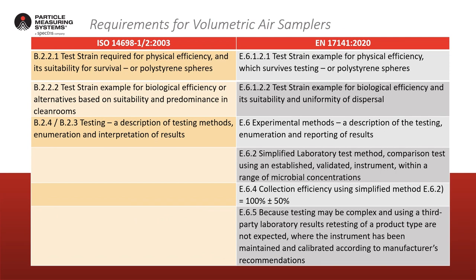Comparing ISO 14698 versus EN 17141, the test strain requirements and test methods are defined for both standards. Section E6-2 of EN 17141 talks about a simplified laboratory test method — comparison against an established validated instrument. If no provided information exists with your sampler for EN 17141, you can run a relatively rudimentary test. Section E6-4 specifies 100 percent plus or minus 50 percent, so providing results are within that acceptable range, the test performed in an open environment is considered a better reflection of day-to-day sampling conditions.